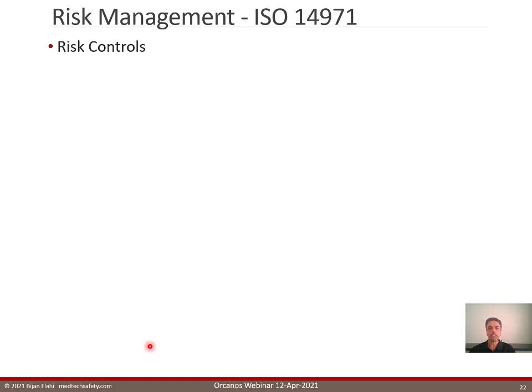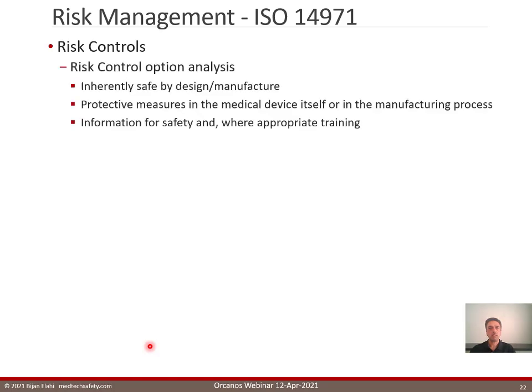Now we come to the next activity in the process, which is risk controls. The standard says do risk control option analysis. There are 3 options that we are given in the order of preference. First is to make your device inherently safe by design or manufacture. So this means your device is just safe by itself. There is nothing the user needs to know or do. It's just safe by itself. And you can achieve this either in your design or in the manufacturing process.